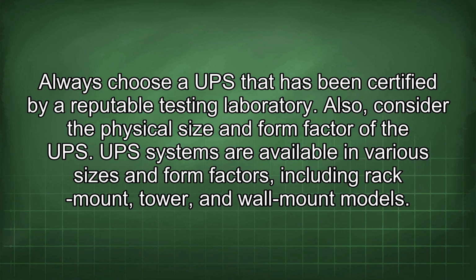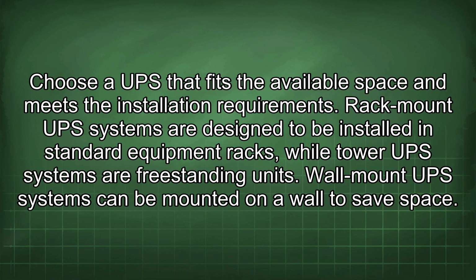Also, consider the physical size and form factor of the UPS. UPS systems are available in various sizes and form factors, including rack mount, tower, and wall mount models. Choose a UPS that fits the available space and meets the installation requirements. Rack mount UPS systems are designed to be installed in standard equipment racks, while tower UPS systems are freestanding units. Wall mount UPS systems can be mounted on a wall to save space.